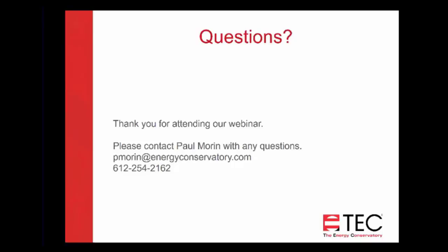This I thought was a good question. Does the RESNET single point test standard automatically add 10%? The RESNET standard does require that if you do a single point test, you add 10% to the results, but our app does not add that 10%. Does it make density corrections for temperature and elevation? The answer to that is yes. You add the temperature and elevation in there, and it does that density correction.